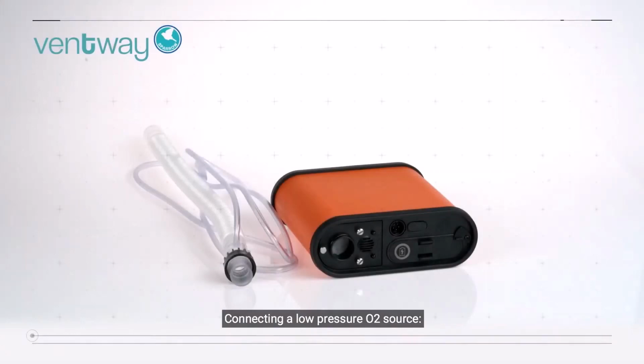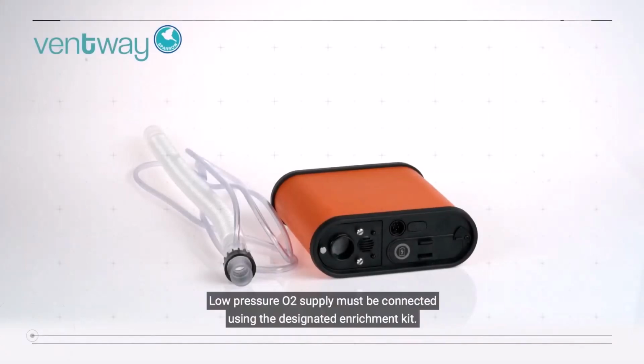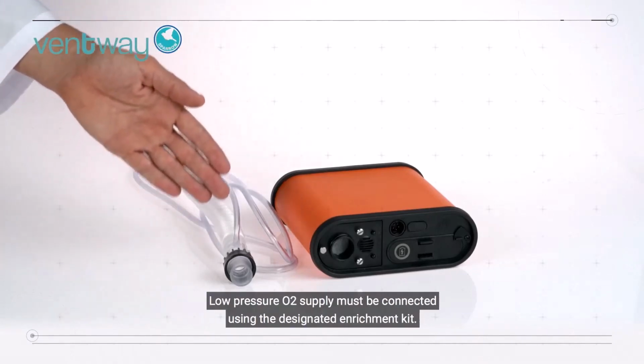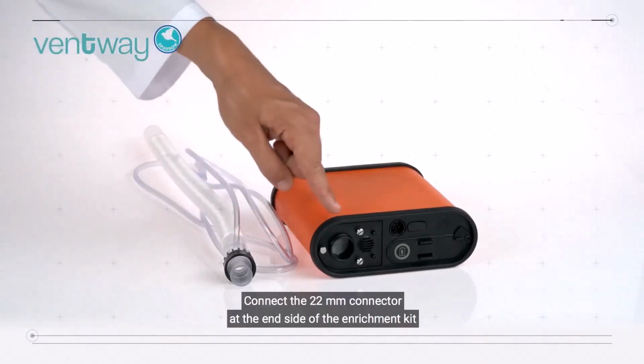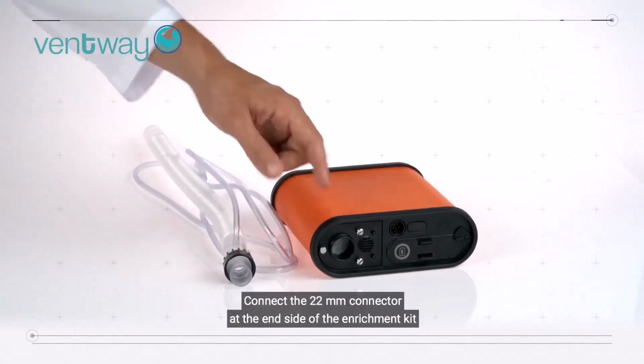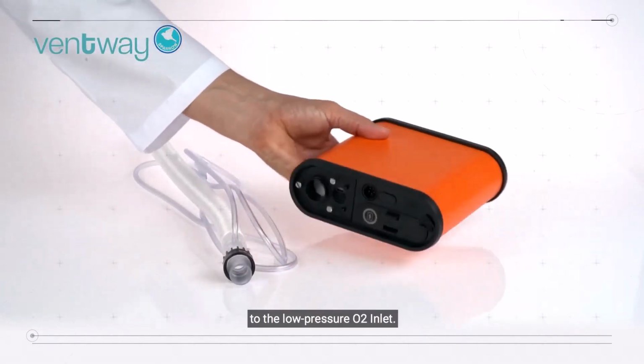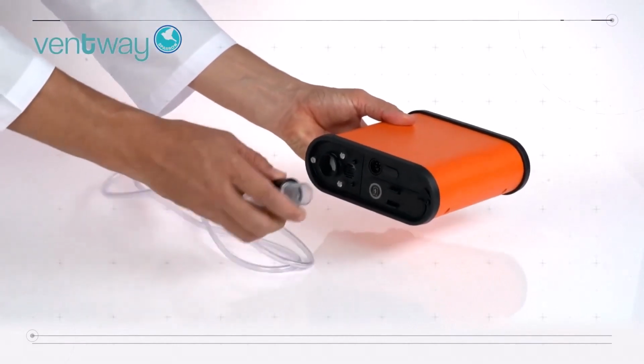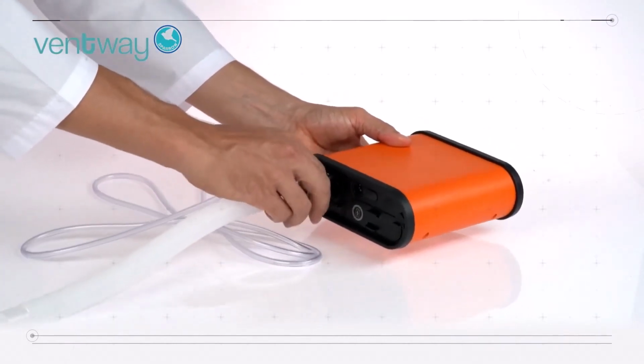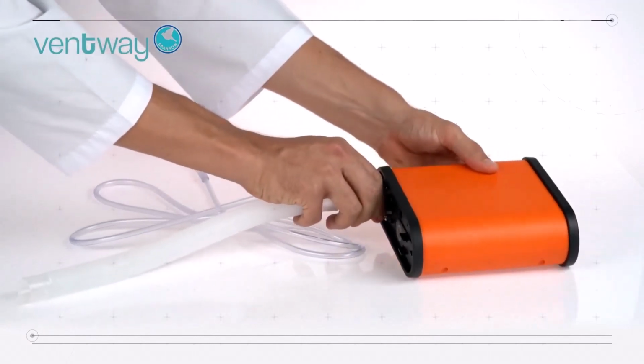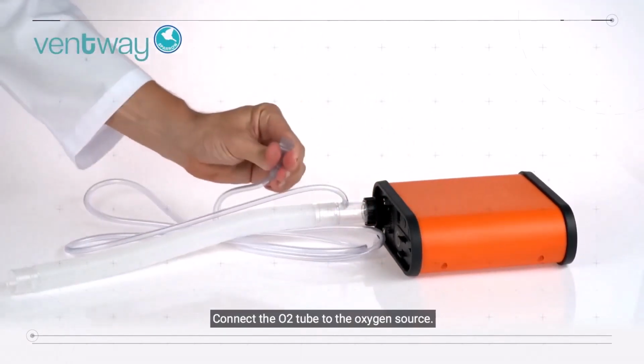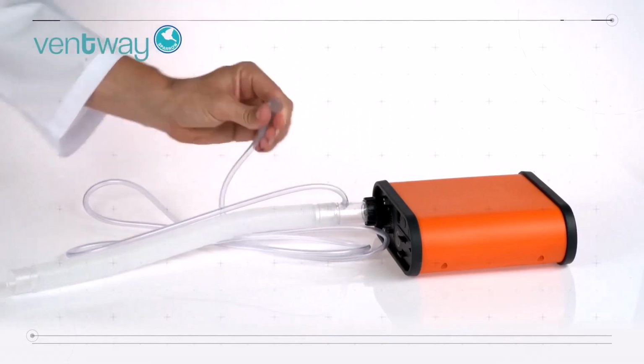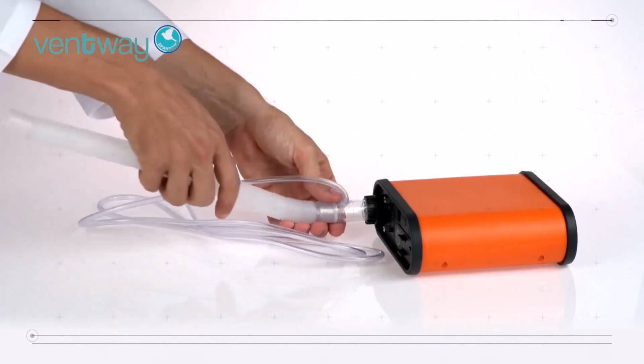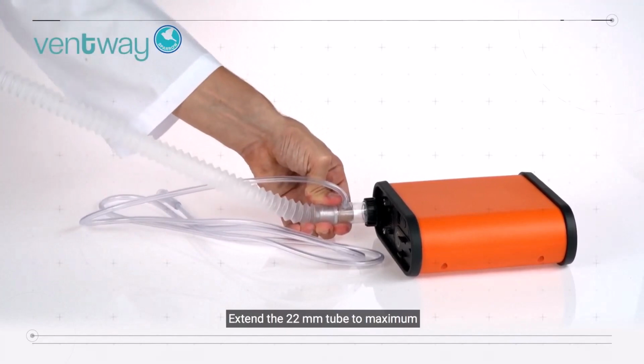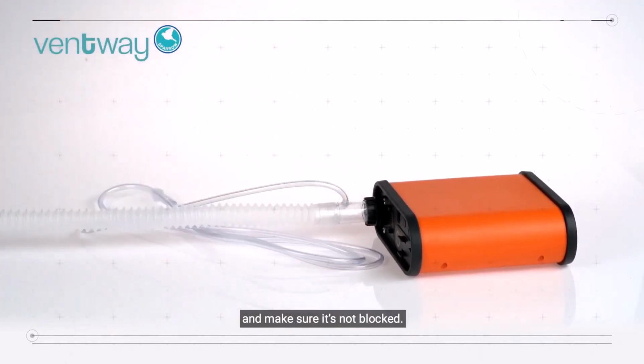Connecting a low-pressure O2 source. Low-pressure O2 supply must be connected using the designated enrichment kit. Connect the 22mm connector at the end side of the enrichment kit to the low-pressure O2 inlet. Connect the O2 tube to the oxygen source. Extend the 22mm tube to maximum and make sure it's not blocked.